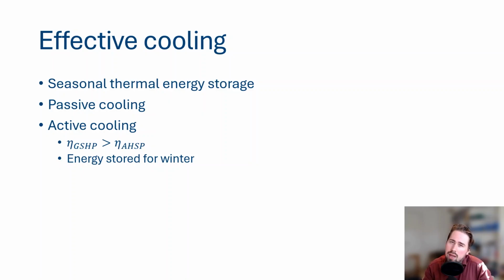Now, in really warm climates like Spain, Italy and Australia, you can also use active cooling. And we talked about the combination of active and passive cooling in the past for commercial buildings and offices. But when you're active cooling, we again have the same story as before. Your ground source heat pump is more efficient than your air source heat pump, because your ground temperature will be lower than your air temperature. In these warm Mediterranean climates, when it's 40 degrees outside and you want to cool your building, it's not 40 degrees in the ground. So your heat pump is also working efficiently.